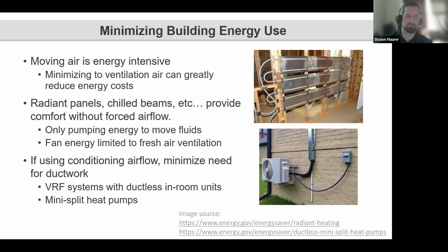So optimizing that DCV system is going to help minimize ventilation energy consumption, and then minimizing your building energy consumption through minimizing how much ventilation air you have to move through the building. Again, as we touched on with radiant systems, if you're providing radiant heat and radiant cooling in a space for that direct sensible control, then your ventilation air is limited to just what it needs to provide your ASHRAE ventilation rates. And comfort control is then provided by direct equipment in the space or a radiant system. Radiant panels, chilled beams can provide that comfort without forced airflow. You're limited just to the energy for pumping fluids through those radiant structures.